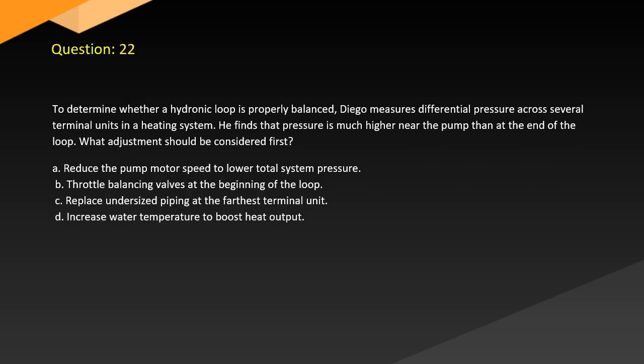Question 22. To determine whether a hydronic loop is properly balanced, Diego measures differential pressure across several terminal units in a heating system. He finds the pressure is much higher near the pump than at the end of the loop. What adjustment should be considered first? A. Reduce the pump motor speed to lower total system pressure. B. Throttle balancing valves at the beginning of the loop. C. Replace undersized piping at the farthest terminal unit. D. Increase water temperature to boost heat output.